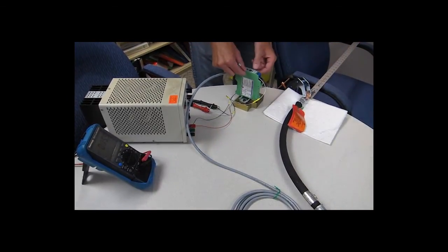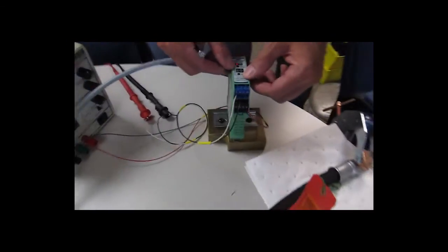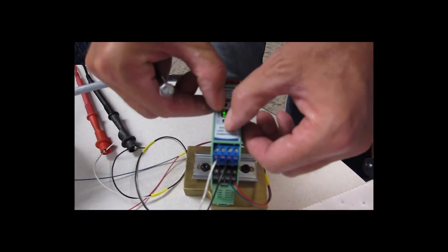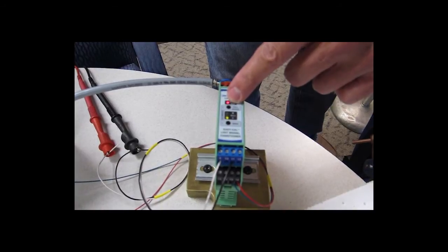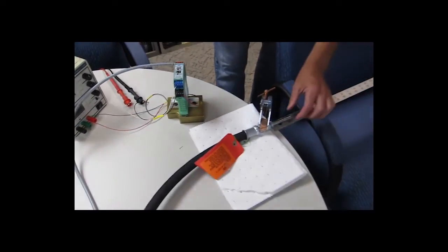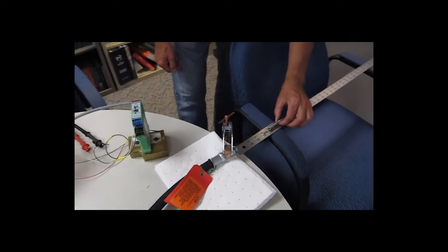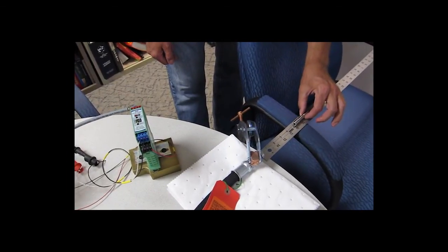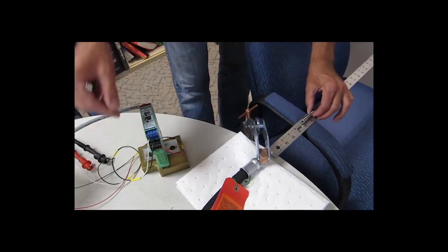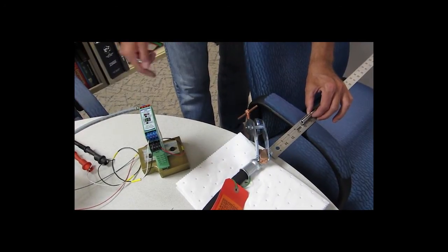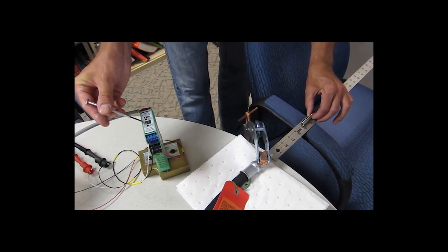So again, we'll put the signal conditioner into calibration mode by pushing both buttons until we get a blinking LED. Let us say that the application is fully zero or fully retracted at five inches. So we'll move it to five inches and press zero. And we'll wait for these LEDs to stop flashing.